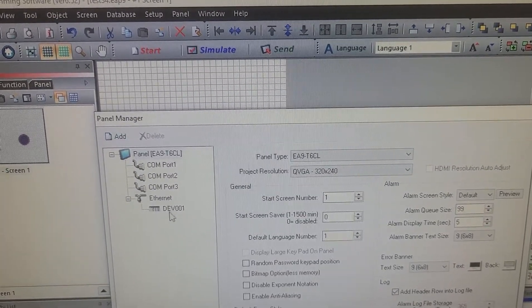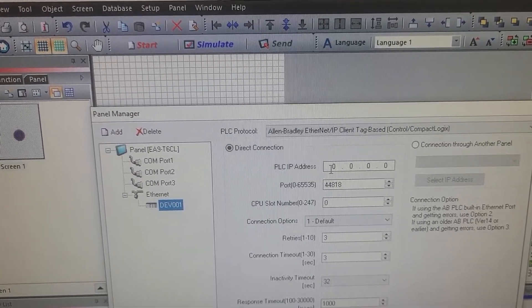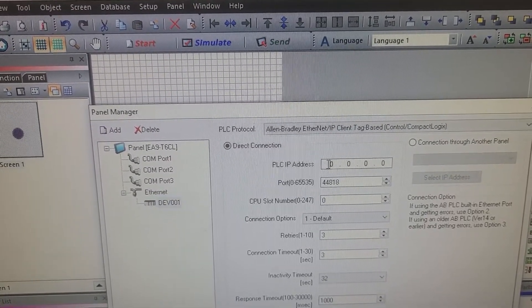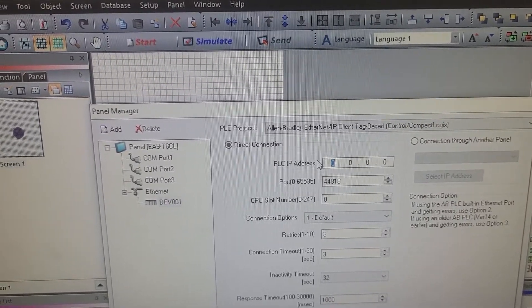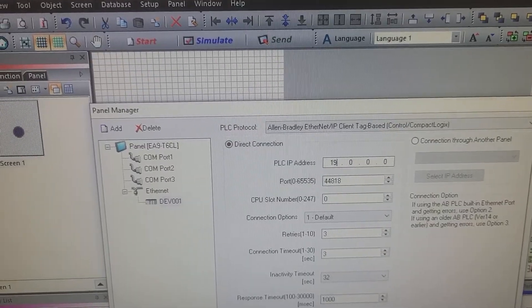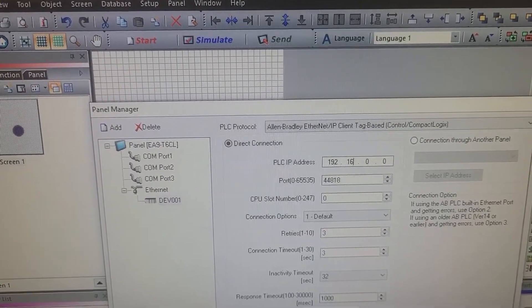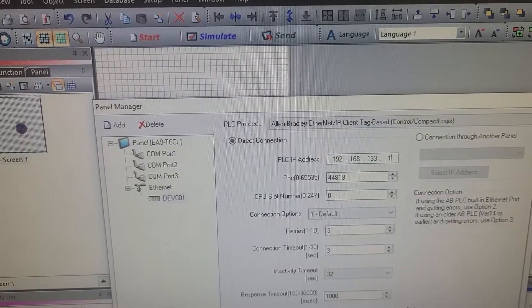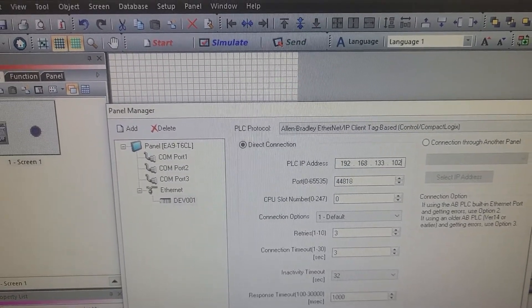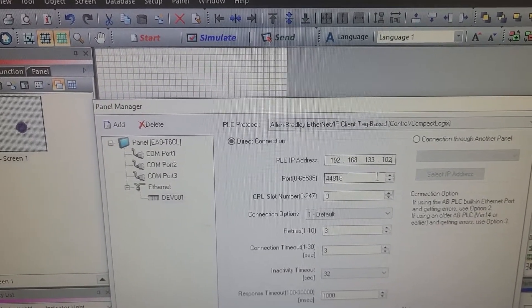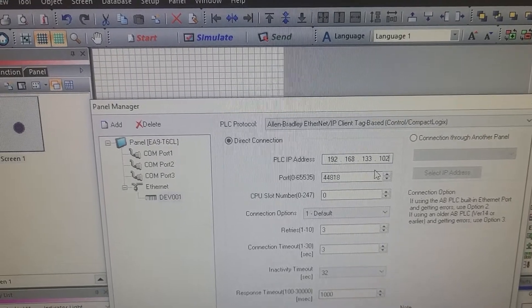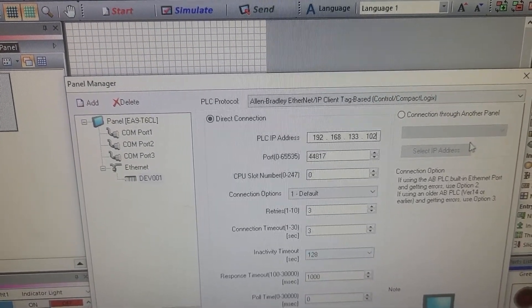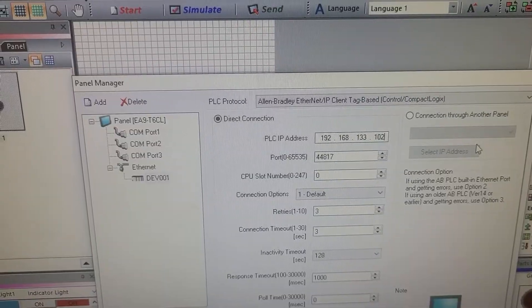If you go into Panel Manager and click on Device 1, right here you'll see that the PLC address all shows zero. This is where you need to actually go in and type it in — and not the IP address of the C-More panel, but the IP address of the PLC that you're downloading to. Once you do that, you should be good to go.